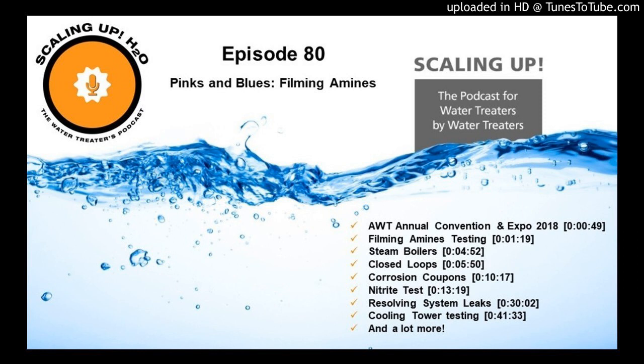You are testing for that residual, and that means that all of the nitrite is used up where it needs to be used up, and that's what's giving you a residual. So you do that, you have that residual, and now you're going to add 1 pound per 1,000 gallons. So you're going to estimate about how many gallons you have.